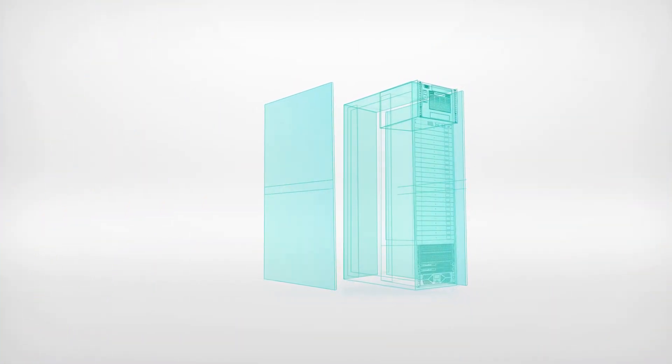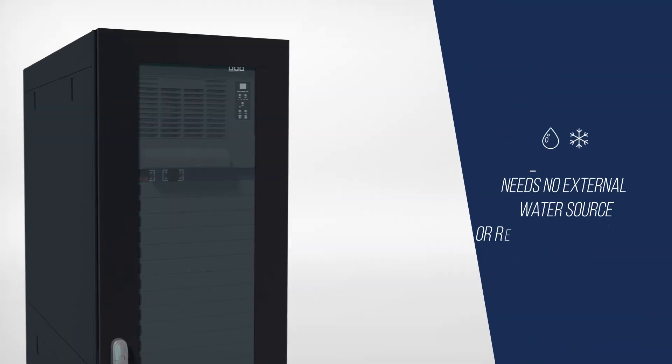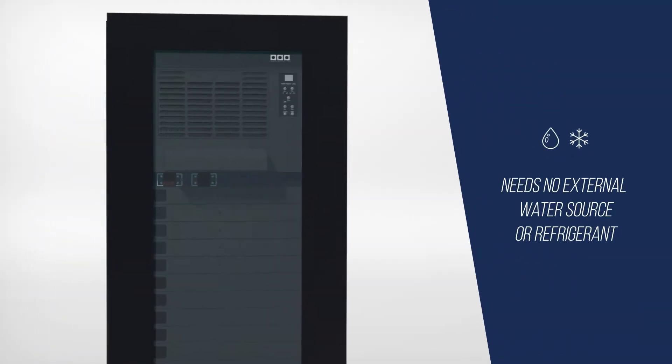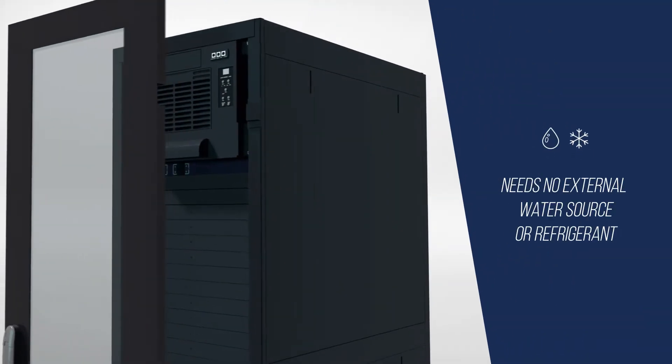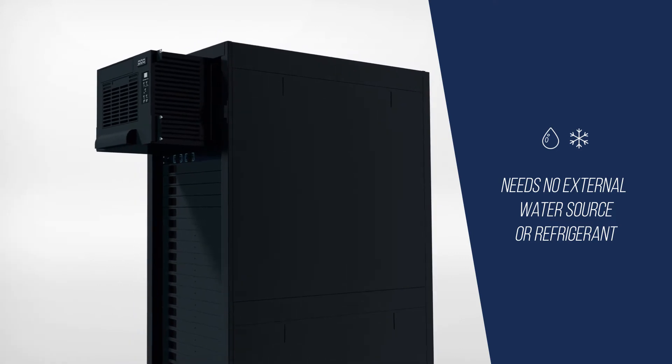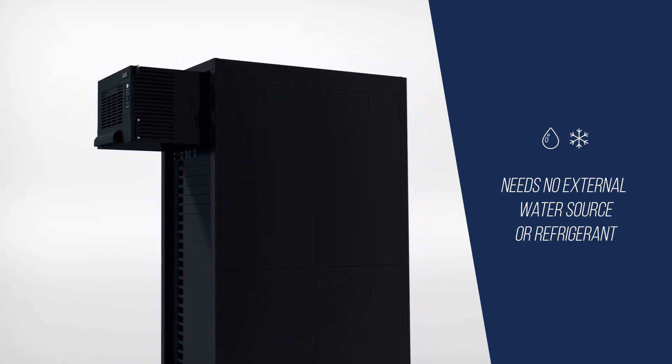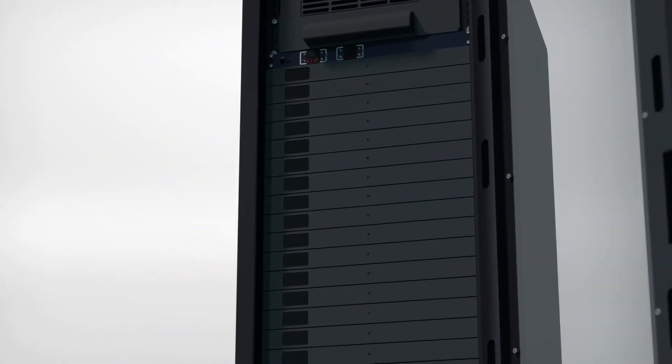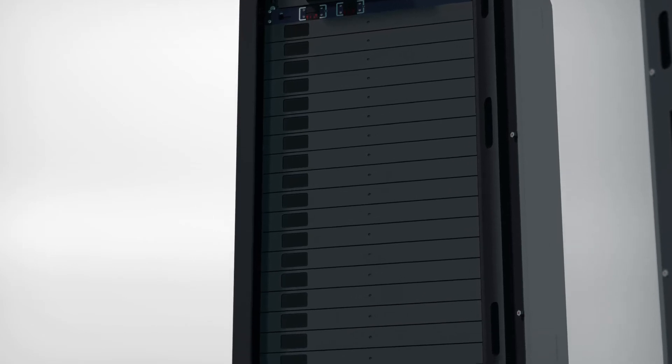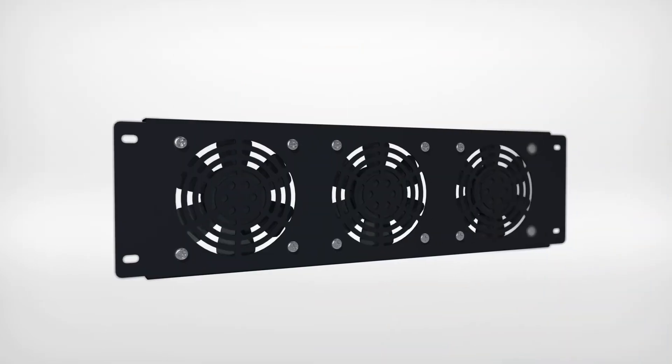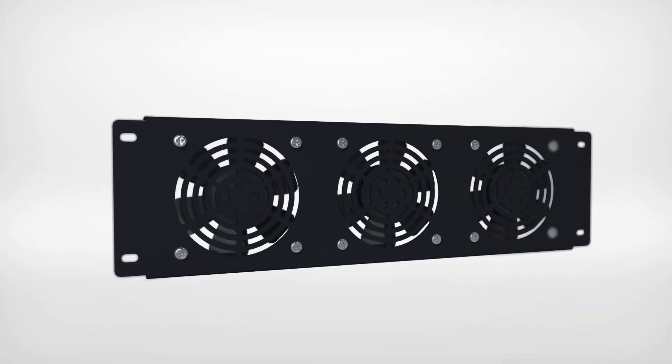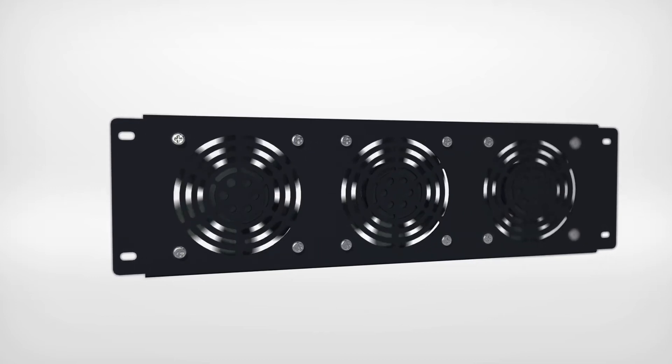With its built-in cooling, the FlexIT OIB Rack requires just 8U of space to cool up to 2.5 kilowatts of heat load. The self-contained unit needs no external water source or refrigerant. Pre-installed blanking panels ensure optimum airflow. When temperatures exceed a configurable threshold, smart fans automatically turn on.